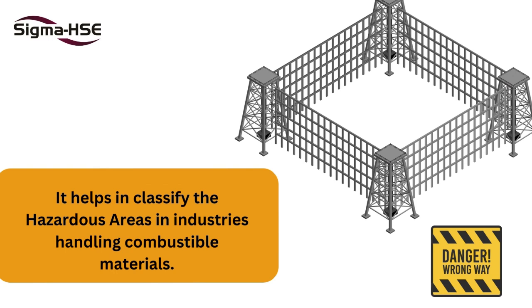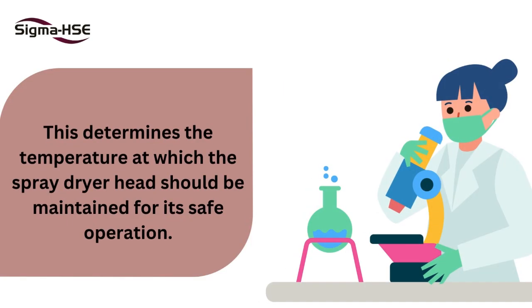It helps in classifying the hazardous areas in industries handling combustible materials. It also determines the temperature class for equipment selection during hazardous area classification. This determines the temperature at which the spray dryer head should be maintained for its safe operation.